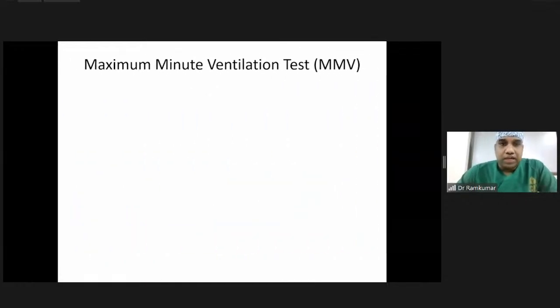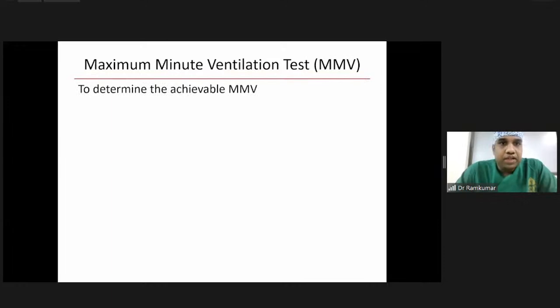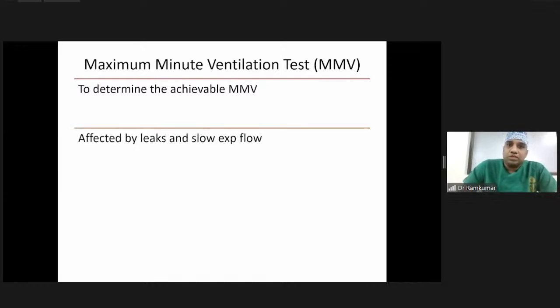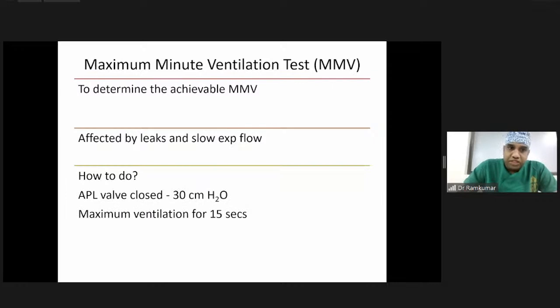This is how it is tested, and this is the way you should use it. This is a definition kind that should be used in your practice or in your study. And coming to other performance tests is the maximum minute ventilation test. This is to determine what is the actual maximum minute ventilation, because if there is a leak or a slow expiratory flow, that is going to affect the maximum minute ventilation which is achieved for the patient.